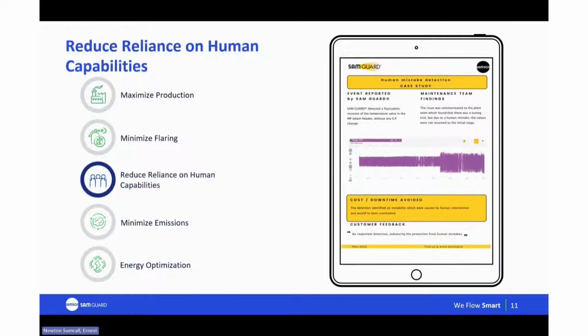In another one, SAM GUARD picked up on a temperature fluctuation. So just in a medium pressure steam header, and even though the set point hadn't changed, there was a temperature fluctuation, and that's a sign something wasn't quite right. So it triggered an alert. The plant team looked into it and found that someone had run a tuning trial, but they didn't reset the values back to their original settings afterwards. So simple human error caused the fluctuation, and the customer called this detection critical. It highlighted an instability caused by human error, something they admitted would have been easy to miss without SAM GUARD.